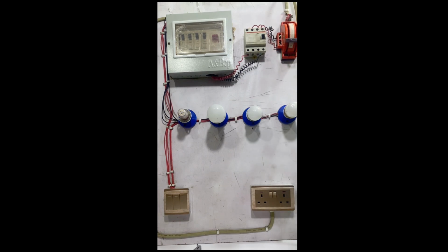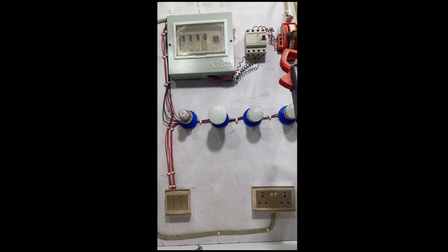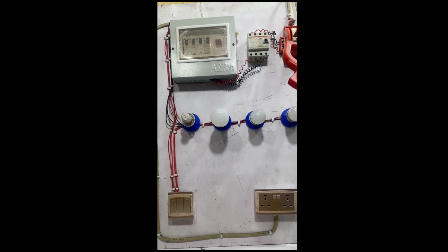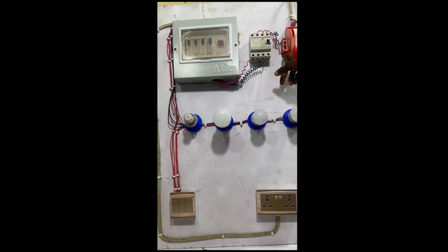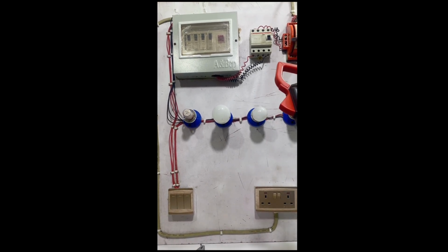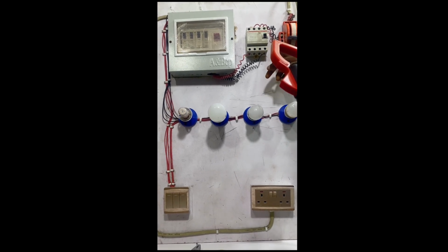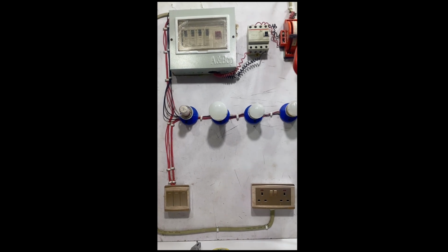The reason is that the changeover is at neutral position, neither getting the supply from generator nor getting the supply from NEPA. So it's only when you take it up that you are going to get the supply voltage from the NEPA, and it will automatically give you a load voltage from the output of the changeover. Now let's see how that works. All right, that is it.